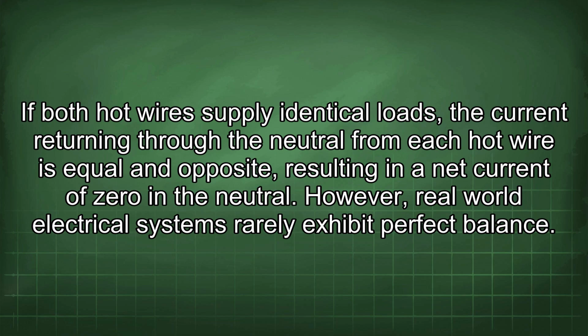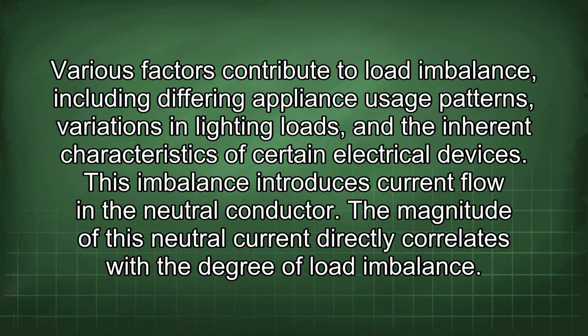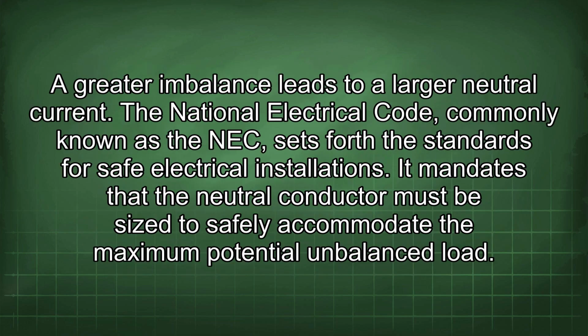However, real-world electrical systems rarely exhibit perfect balance. Various factors contribute to load imbalance, including differing appliance usage patterns, variations in lighting loads, and the inherent characteristics of certain electrical devices. This imbalance introduces current flow in the neutral conductor. The magnitude of this neutral current directly correlates with the degree of load imbalance. A greater imbalance leads to a larger neutral current.